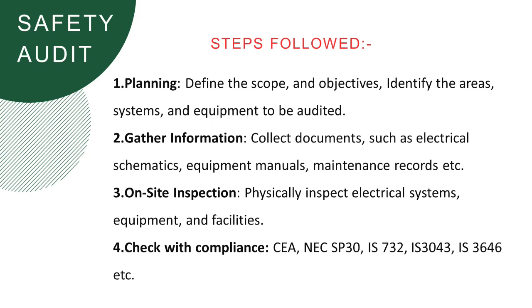The on-site inspection is carried out according to applicable regulations. The main regulations followed in an electrical safety audit include CEA — Central Electricity Authority of India — electrical safety regulations and rules. Additionally, Indian standards for electrical installation IS 732, Indian standard for earthing IS 3043, Indian standard for lighting IS 3646 for lux levels in the premises, as well as national building codes and national electrical codes are followed.